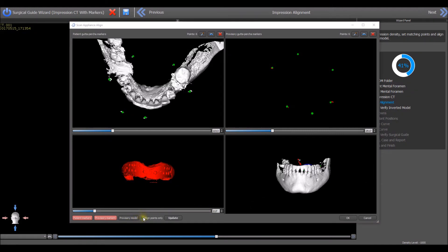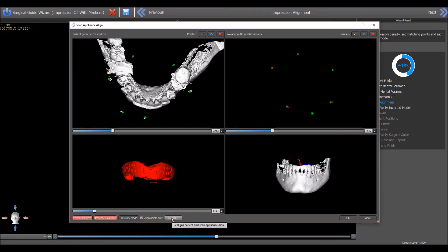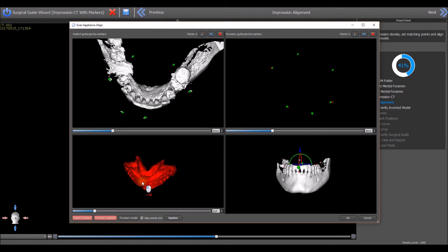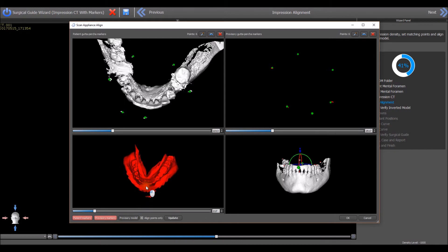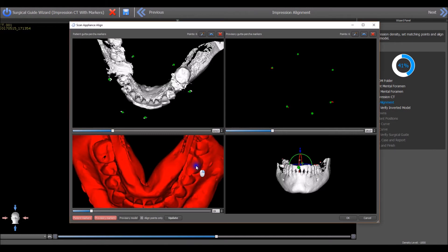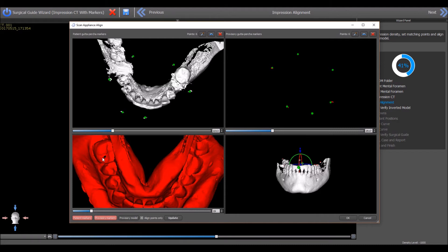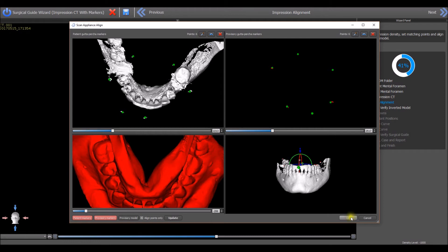Left-click the Align Points Only box and then left-click the Update button to align the two sets of markers in the bottom right view. Finally, hold down the left mouse button and move the mouse to rotate the Impression Scan in the bottom left view to see if there are any holes in the impression. Hold down the right mouse button and move the mouse forward to zoom in. If there are holes, this is an indication that the Impression Scan tray was not prepared properly according to the steps outlined in the beginning of this video. If there are tiny holes, lower the slider underneath the scan in very small increments until the holes have been filled. Then press the OK button.